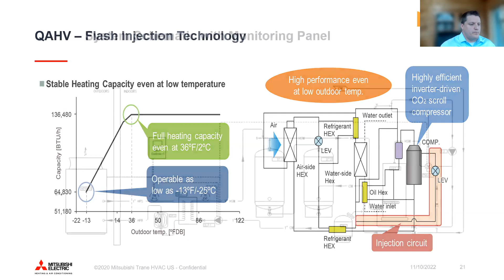So this is really what our system ends up looking like from a schematic view. And this slide I'll take a little bit more time on, but it really breaks down to three major components. So you can see what we'll call the primary side. That is our heat pump with water lines to a brazed plate heat exchanger that we use in our configuration, mainly just because of the US water quality. It really is much more beneficial to have an easily cleanable heat exchanger that's low cost in case there was any damage or anything like that in this application.